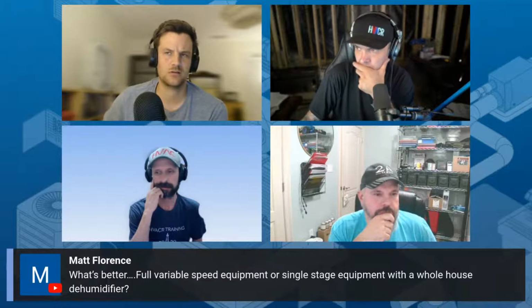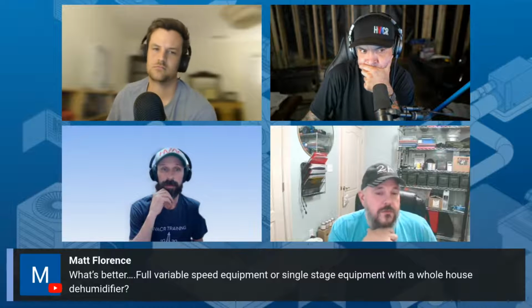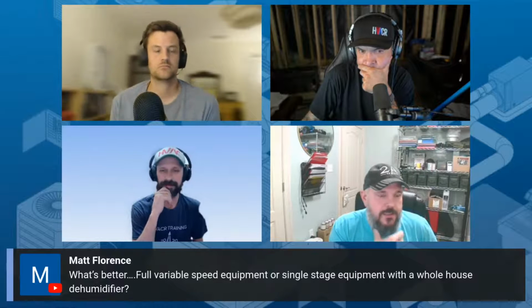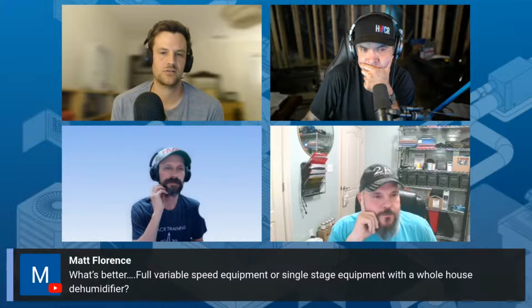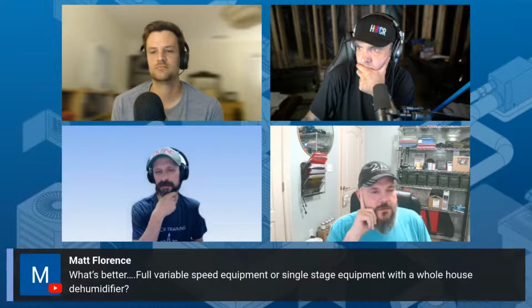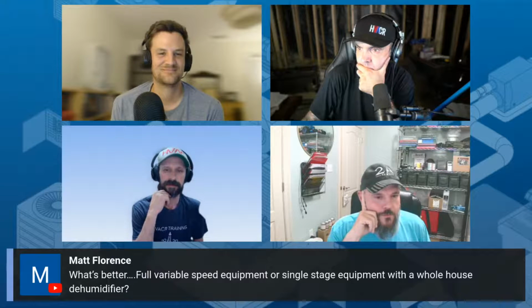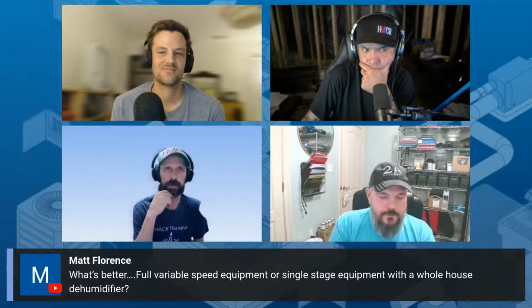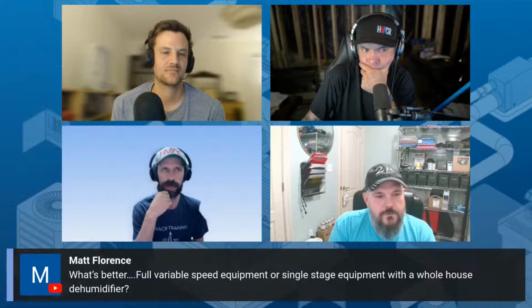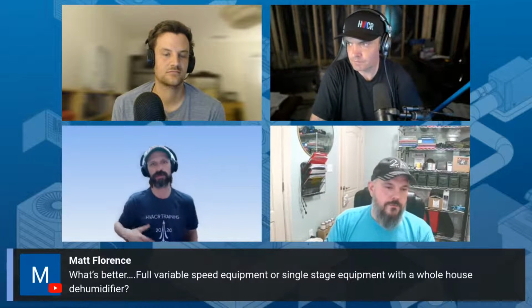Talk us through a little bit about what you guys do differently for inverter systems in terms of installs. To me, my approach is it gets installed the exact same way. The only difference is you have an inverter versus a single stage compressor. Is there anything you're adding, like surge protection? Oh yeah, it depends on the system and the location. We might do a buck and boost, but every single inverter gets a surge protector for sure. Yeah, we use surge protectors on every one. Technically, if you're doing all the ductwork and everything, there may be considerations of how it's going to run in lower speeds. But for us, the difference would be maybe thermostats and controls and stuff like that.